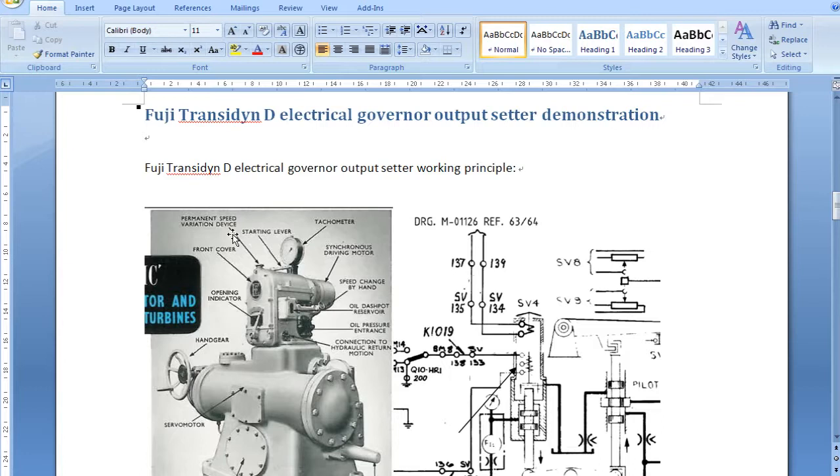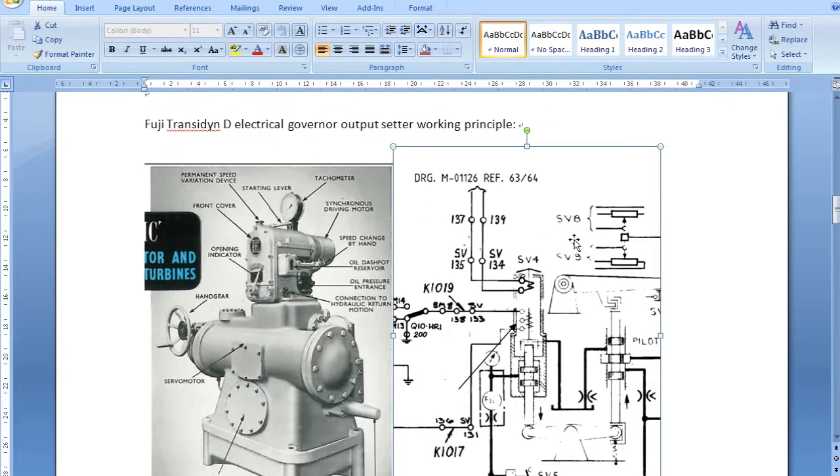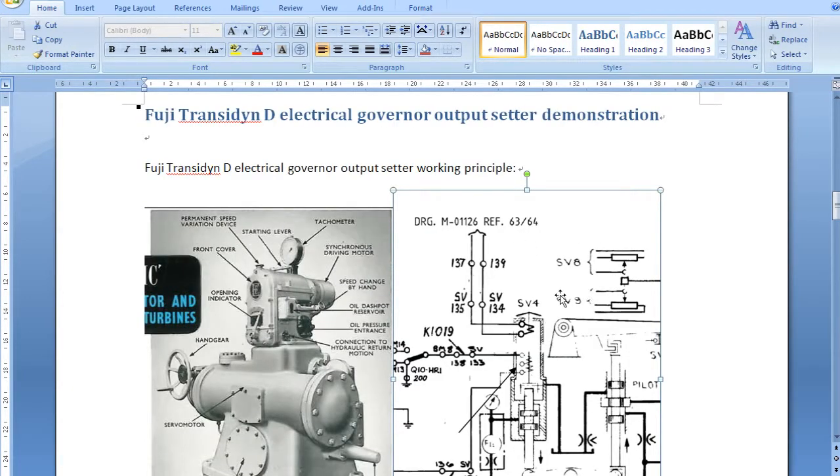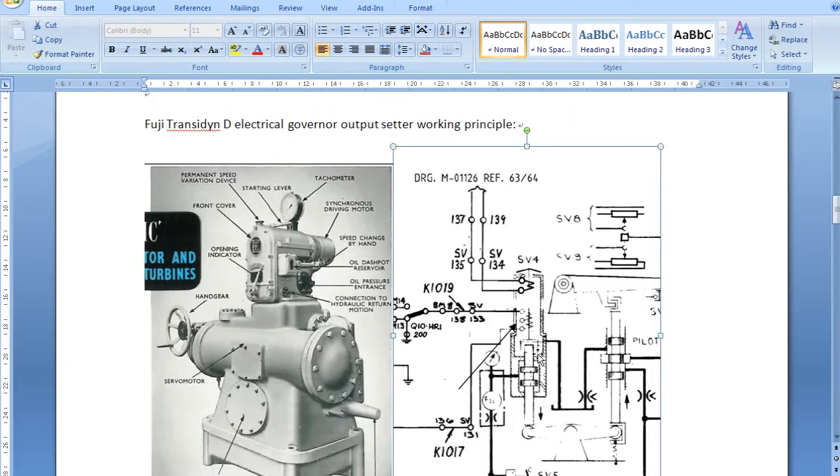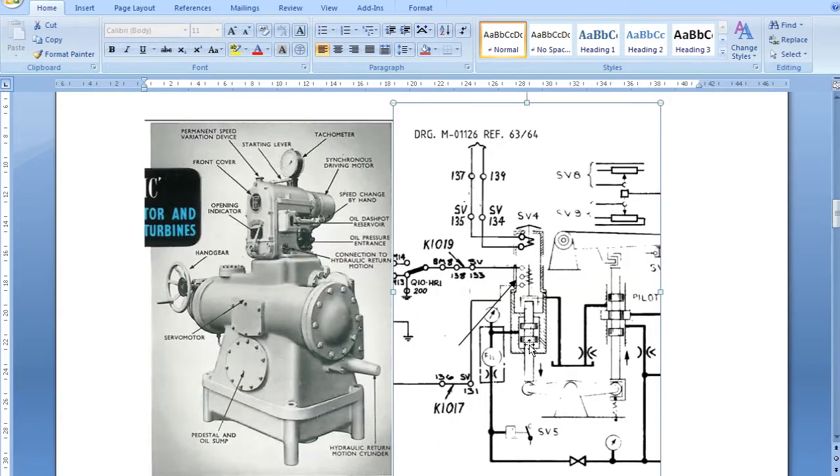But for the other governors, which were developed in the 1970s, there are more and more electrical or even digital components involved. So this is the E20, but I believe the Fuji governor must apply the same sort of idea. It's called the EH actuator, I think. So basically, for those governors, they apply a coil in the actuator to convert the electric signal into a mechanical force to drive the distribution valve here. And after this distribution valve, the rest of the system is pretty much the same as the English Electric, just several mechanical amplifier stages, and eventually to drive the guide vane position.